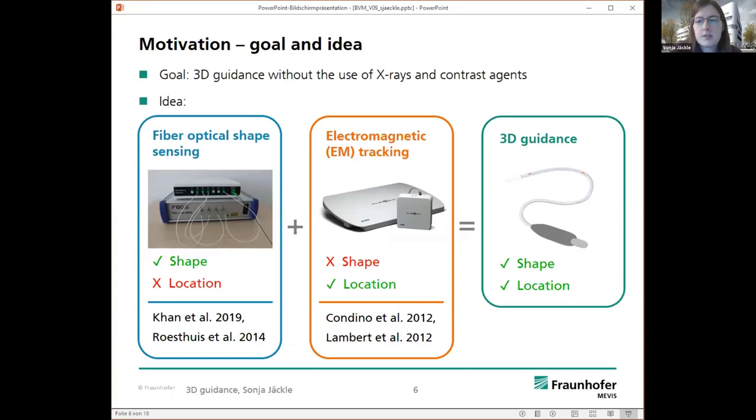And to reach this goal, our idea is to use tracking systems. So the first technology we are using is fiber-optic shape sensing. This allows us to track with optical fibers the shape, but it doesn't give the information where the shape is exactly. And for this task we are using electromagnetic tracking, so the sensors give the location, the position, and the orientation information, but not the shape of continuous instrument. So only for one specific position, you know the location.